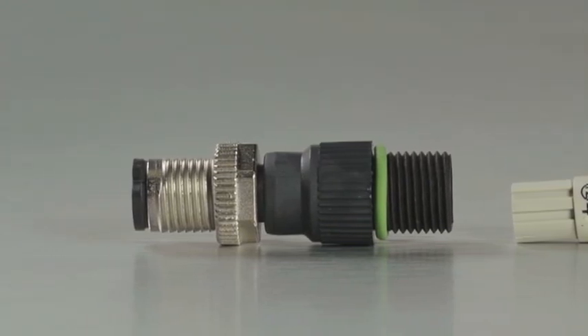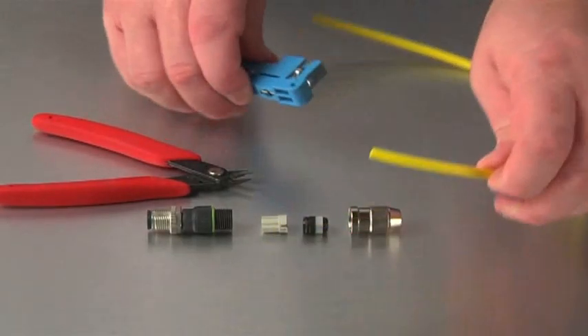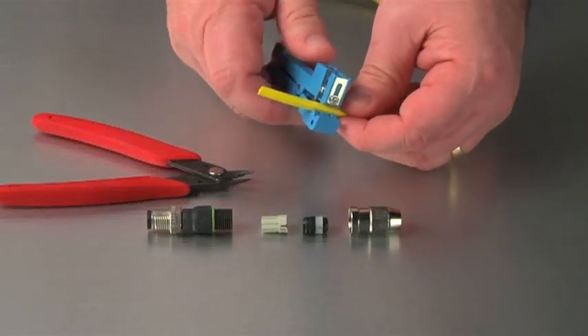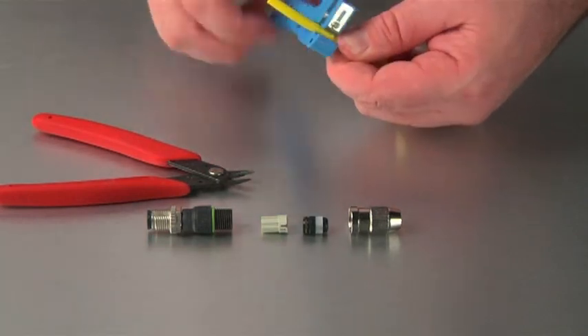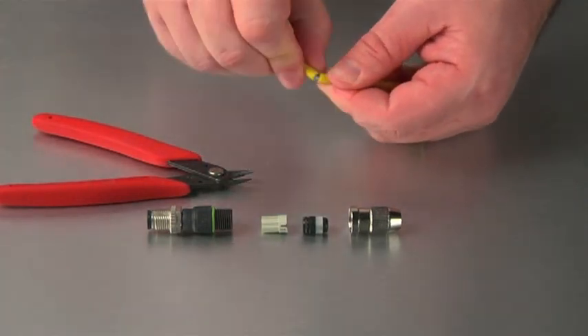Let's go through the steps to assemble an IDC. To begin, remove approximately 25 millimeters minimum of the outer cable jacket from the conductors. Leave the insulating cover on the inner conductors.